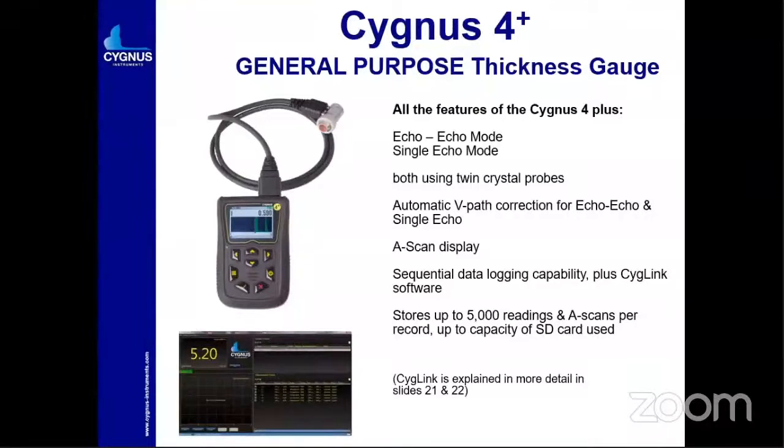Another model is Cygnus 4+, also a general purpose thickness gauge. It can be utilized in both single echo and echo-to-echo modes, both using twin crystal probes. You can use both probe types in this gauge. Another feature is that you can store data up to 5,000 readings, with scan records on an SD card. You can increase the capacity by inserting a bigger card with larger memory. The software allows you to check readings — whatever A-scan or B-scan data you have taken — and transfer it to PC to make reports.